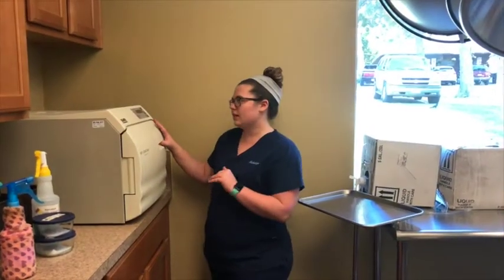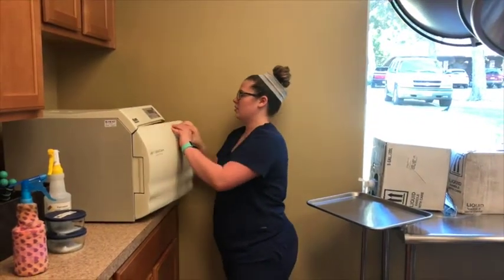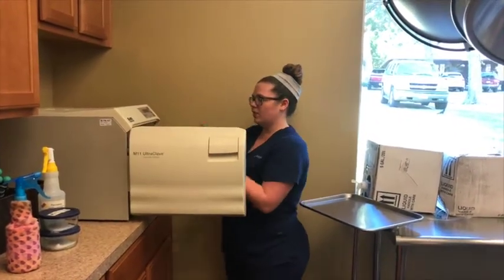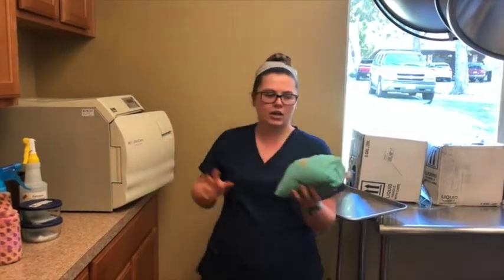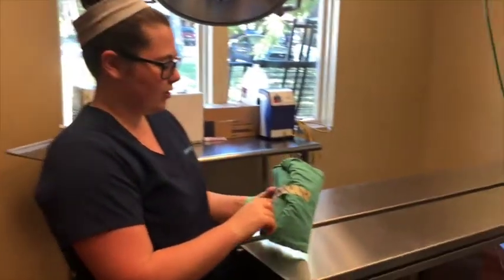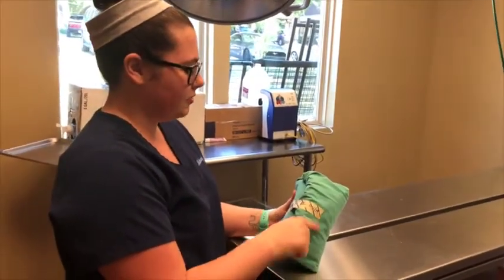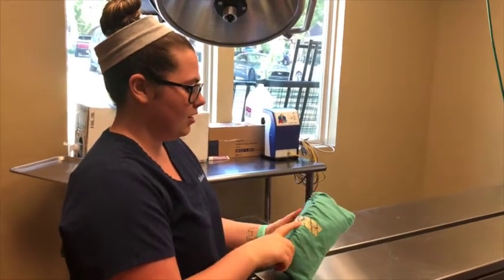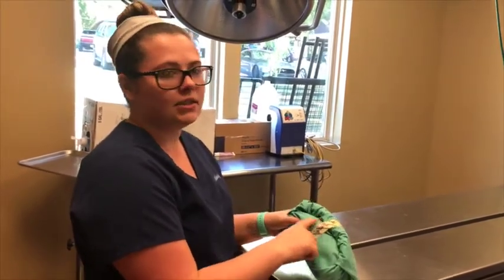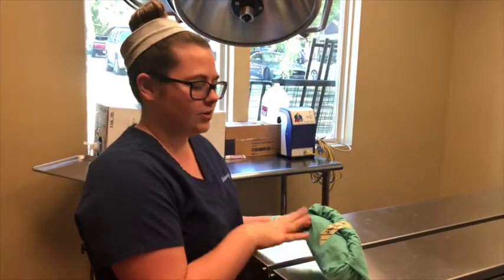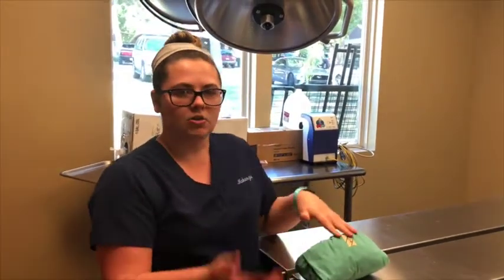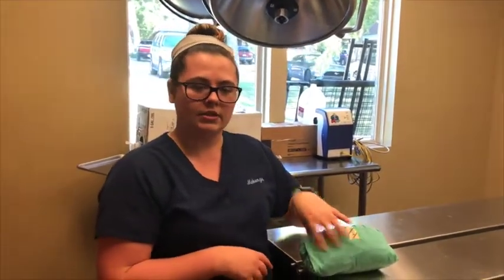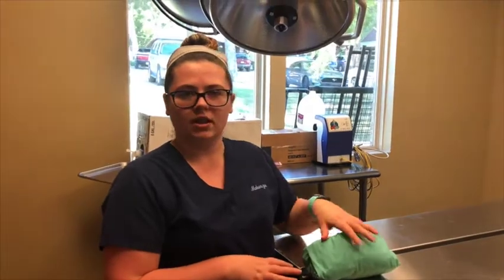So once our autoclave is done, we're going to open it. And we're going to remove our pack that we sterilized. And then, as you can see, it'll have the green, or it'll tell you what surgery pack. So this is our green surgery pack, the date, the initials, and these black lines indicate that it has been sterilized and it is okay to use. Once the doctor does open it up, it does have the OK strip in it that also will need to have turned black to make sure that everything inside of this is also sterilized. And this is a properly sterilized pack.